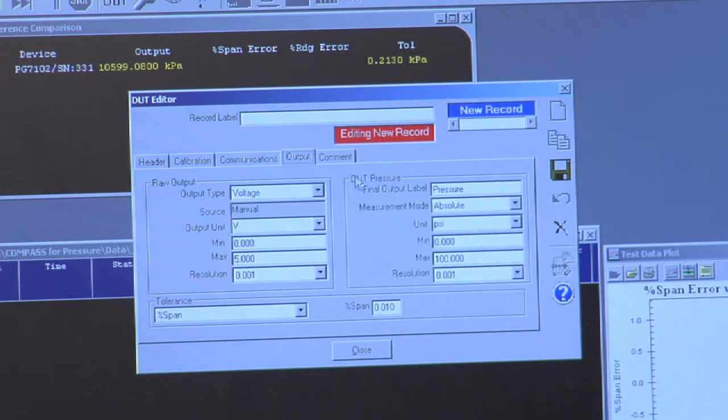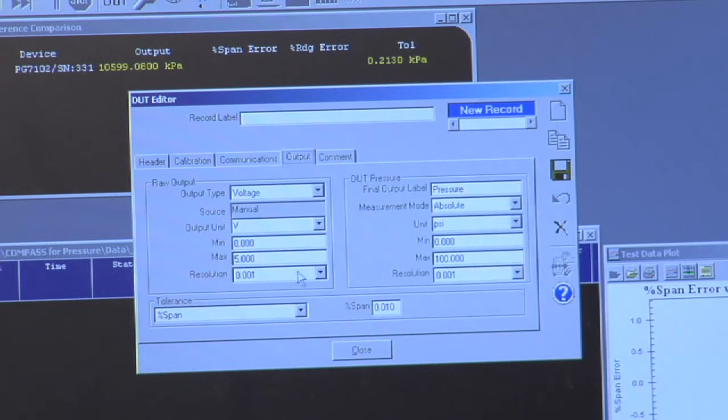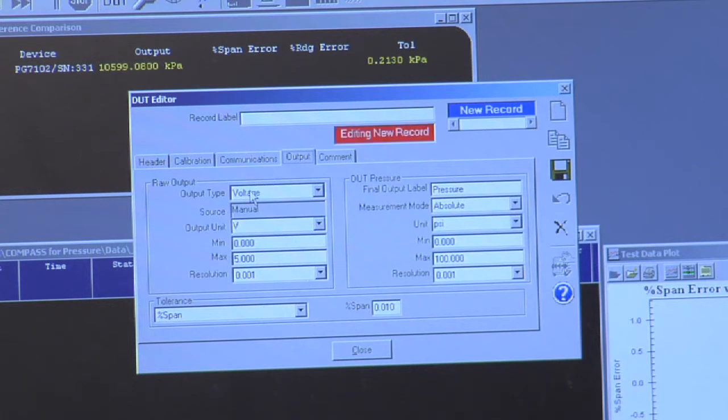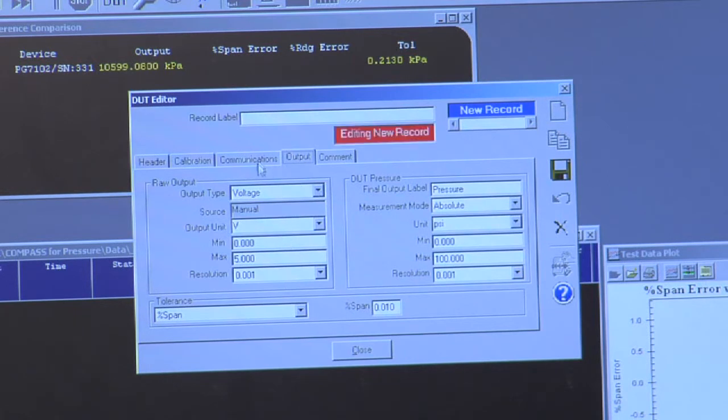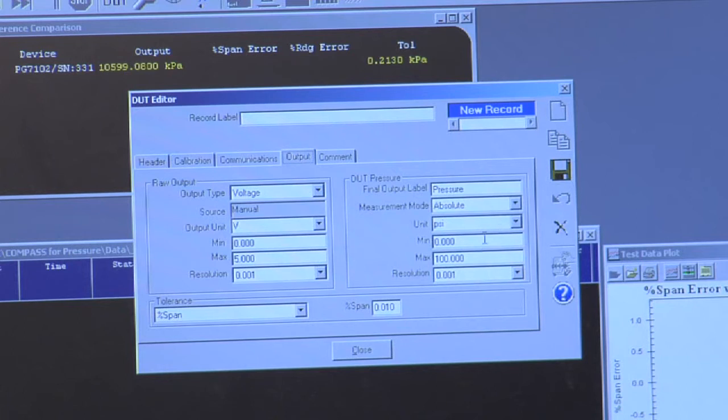I have the output, which defines the relationship of how the instrument fundamentally outputs to how the pressure is determined. So in this example, I have voltage displayed, so the instrument can output 0 to 5 volts, and that would correspond to 0 to 100 PSI.